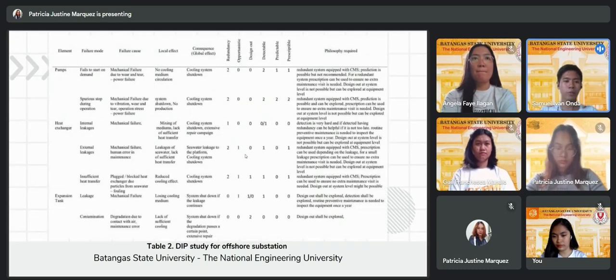And for Table 2, it presents the DIP study for an offshore substation. Table 2 contains an analysis of the failure modes of the three primary functions, which are pumping, cooling, and handling the thermal expansion. Since this is an investigation of failure at the equipment level, failure modes of the components and sub-functions are not being taken into consideration currently.